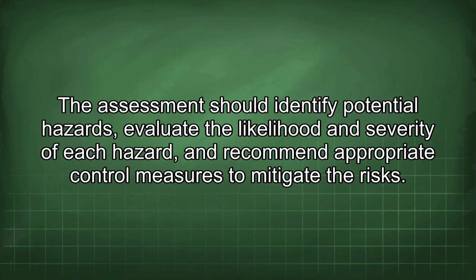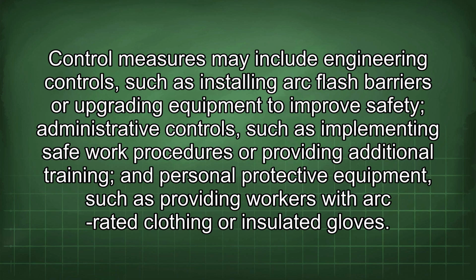The assessment should identify potential hazards, evaluate the likelihood and severity of each hazard, and recommend appropriate control measures to mitigate the risks. Control measures may include engineering controls, such as installing arc flash barriers or upgrading equipment to improve safety, administrative controls, such as implementing safe work procedures or providing additional training, and personal protective equipment, such as providing workers with arc-rated clothing or insulated gloves.